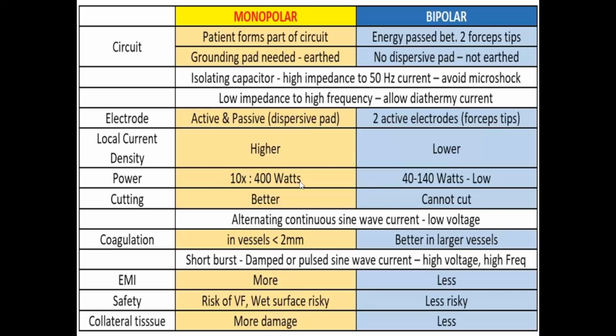Power: you use higher power in monopolar, 400 watts. That's why you can cut, because it's higher power. Bipolar is lower watts, so it can only coagulate. I put yellow for monopolar because it can cut. In bipolar, it can only coagulate. That's why I color it blue. As I mentioned, monopolar can be used to cut. Bipolar cannot cut. For coagulation, monopolar can coagulate vessels of less than 2 millimeters, but bipolar can coagulate better in larger vessels. Okay, it's better for coagulation.